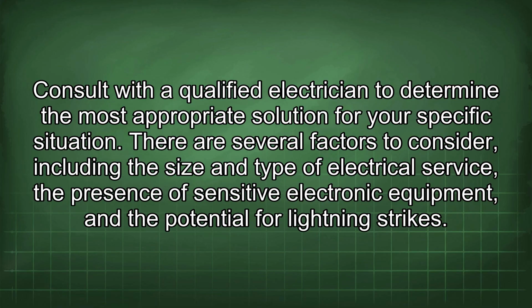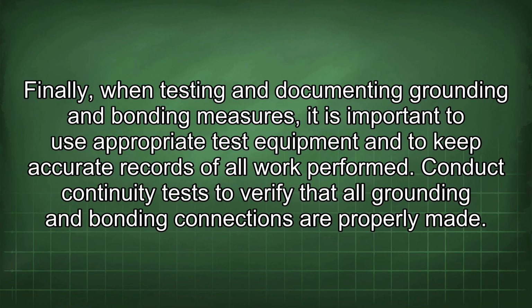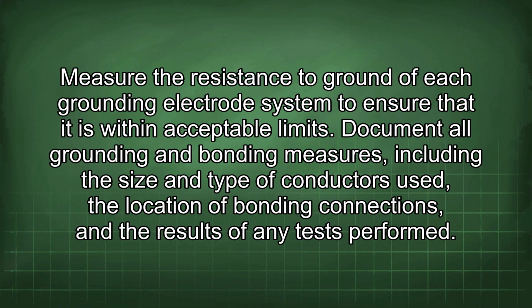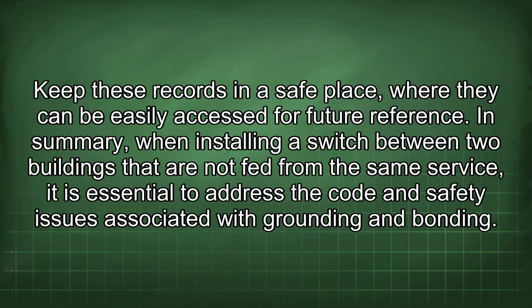There are several factors to consider, including the size and type of electrical service, the presence of sensitive electronic equipment, and the potential for lightning strikes. Finally, when testing and documenting grounding and bonding measures, it is important to use appropriate test equipment and to keep accurate records of all work performed. Conduct continuity tests to verify that all grounding and bonding connections are properly made. Measure the resistance to ground of each grounding electrode system to ensure that it is within acceptable limits. Document all grounding and bonding measures, including the size and type of conductors used, the location of bonding connections, and the results of any tests performed. Keep these records in a safe place, where they can be easily accessed for future reference.